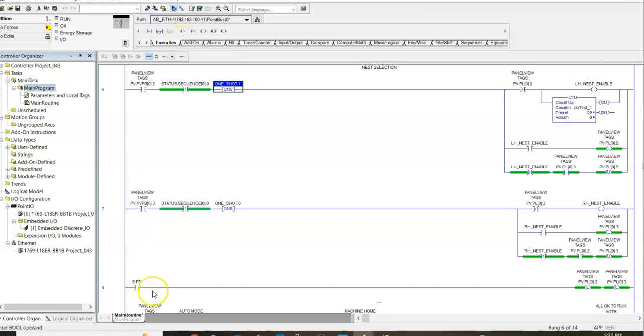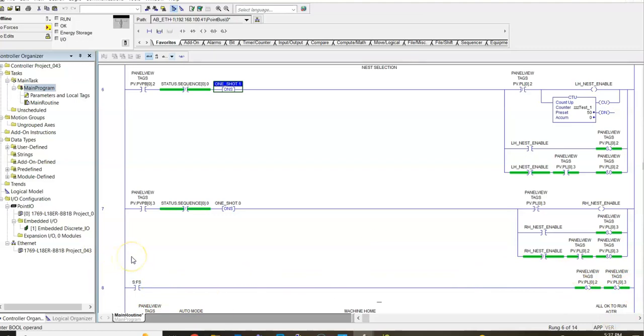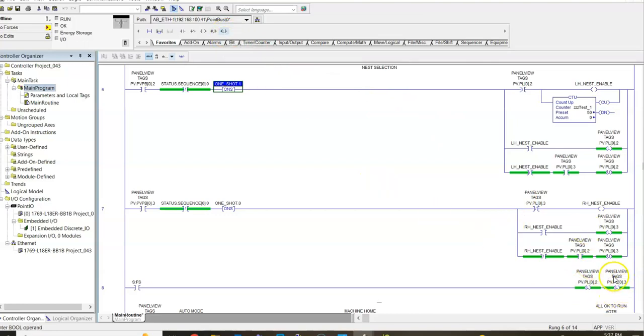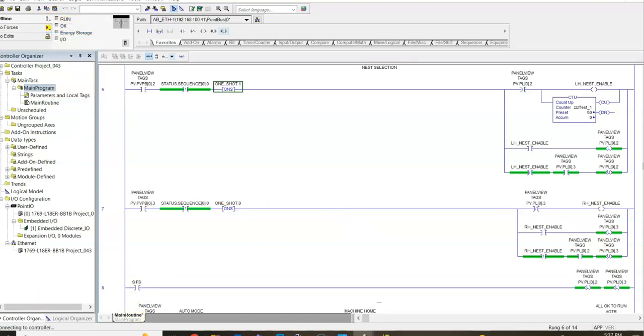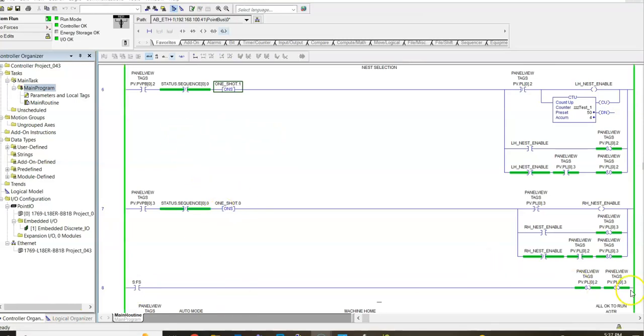The examine if closed instruction. So this instruction right here will close for one scan only, the very first scan as the processor is energized, and it will latch these two bits. This is the latch bit also found on your favorites tab. We'll do both. Once that's done, we'll go ahead and go online.